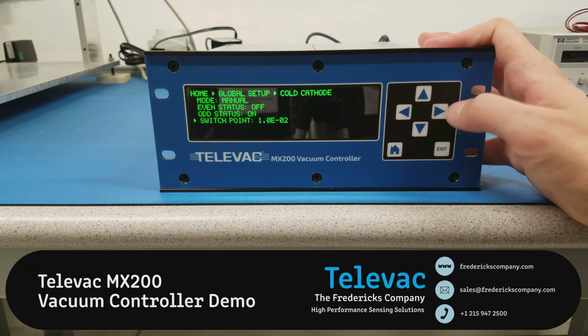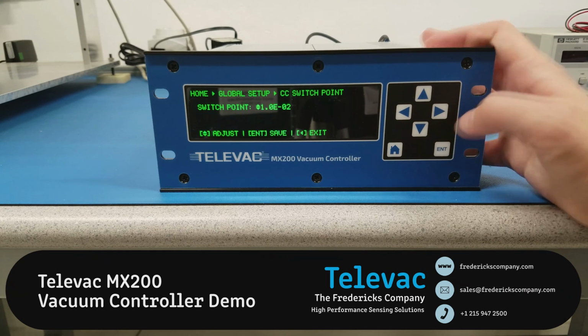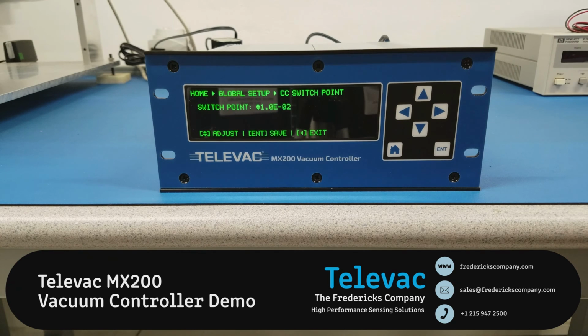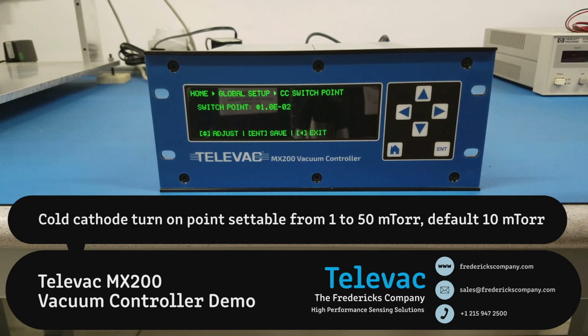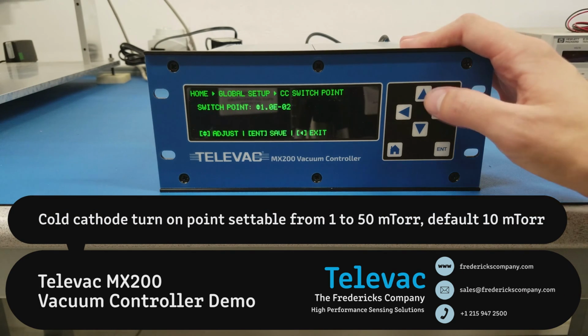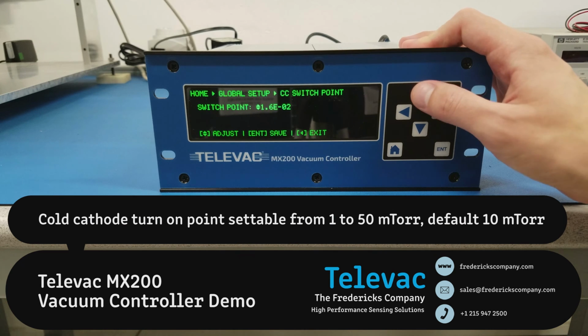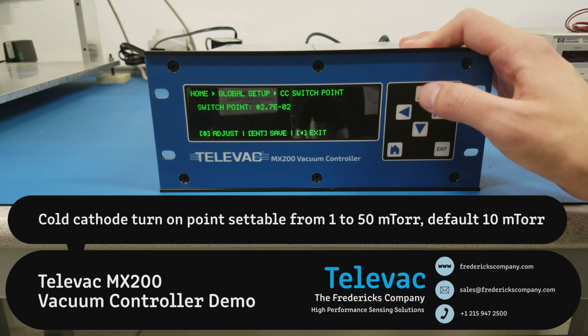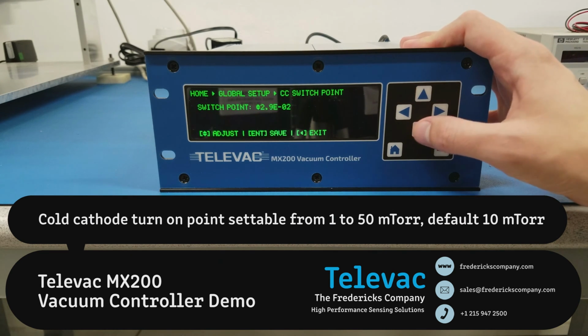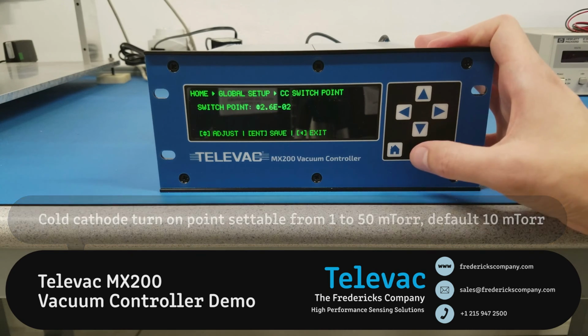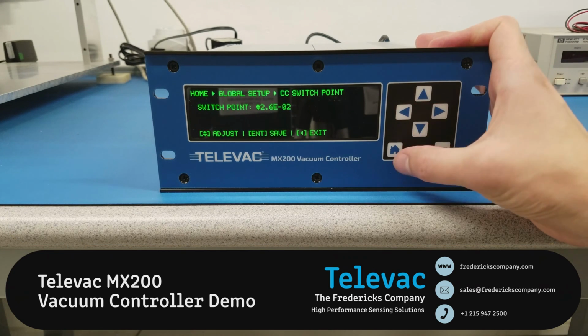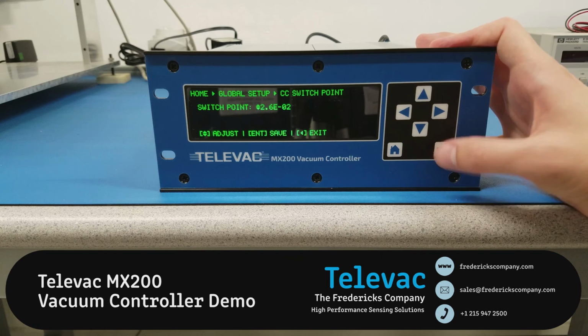So the last thing that we added to this unit that's new is the switch point for the cold cathode. So previously there was a hard switch point of 10 millitorr or 10 microns. Now this value is adjustable from 1 to 50 microns. So you can see here we're adjusting the value up and down. Alright, so let's back out of this. We'll save that value.